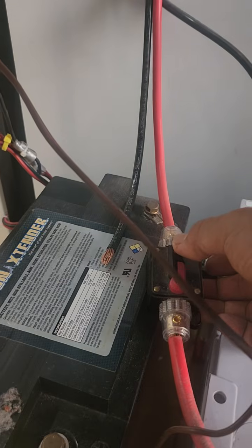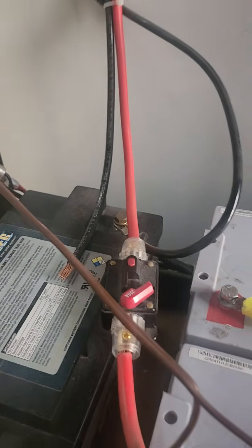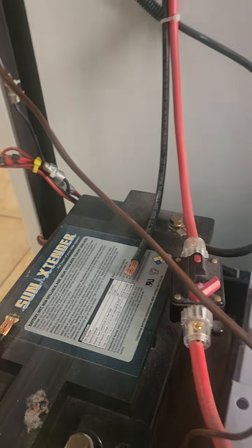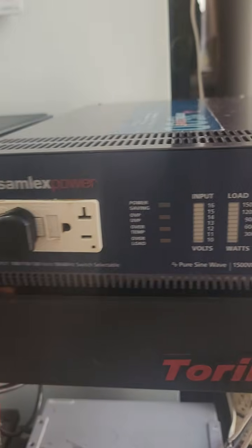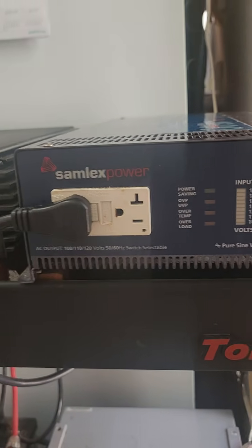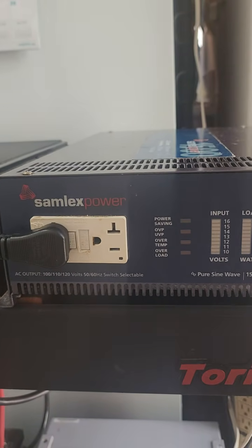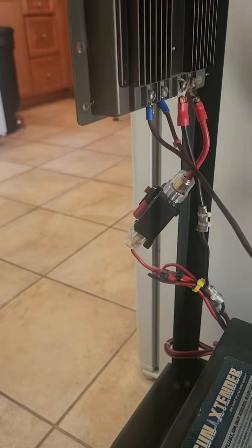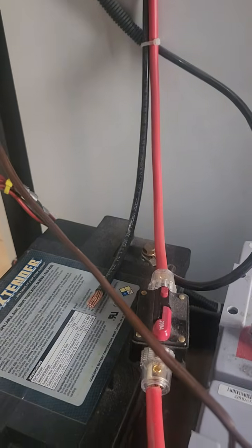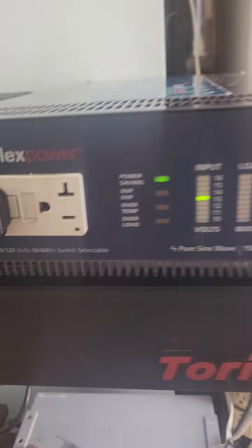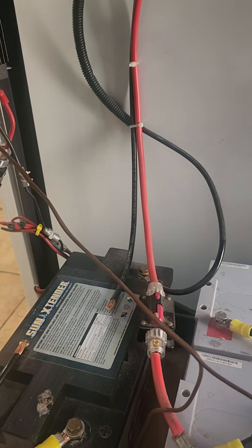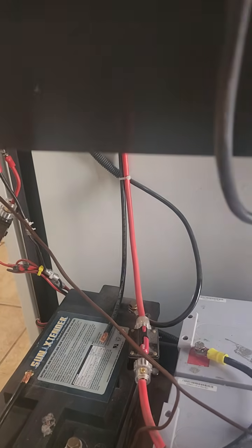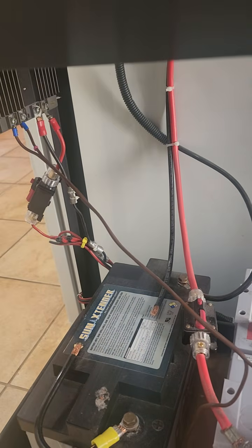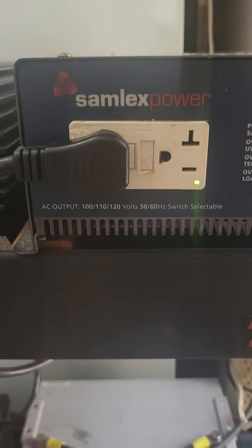And to show you that this is working, I will try to pop out this one. If there is a short, that will pop out. So right now, the inverter is dead. Right? I could pop in this one. I pop it in, and again the inverter is alive. So the main purpose of that circuit breaker between the battery and the inverter is to protect against any large current just in case there will be a short circuit that occurs in the inverter.